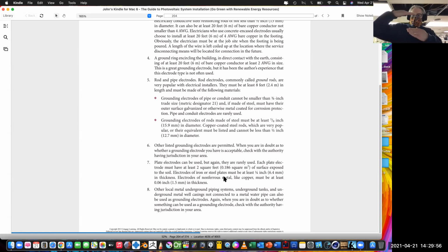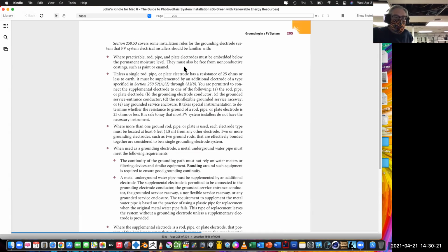It's going to be sticking up about that much. You don't want the thing sticking 2 feet out of the ground. That's not what they're saying. If you are, you're going to trip over it. No, it's going down into the ground. More in the ground is better. Okay? Because you're trying to get as many of those electrons into the earth if you have a fault. So the deeper we go into the earth, the better. So in this case, let's move on.